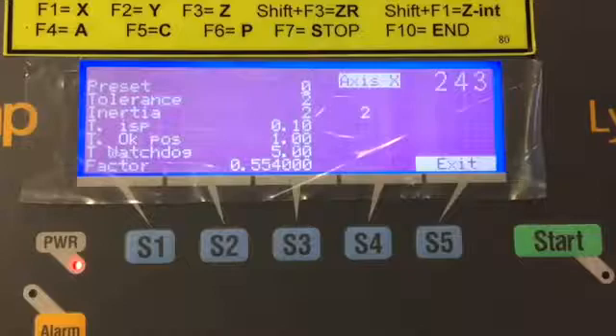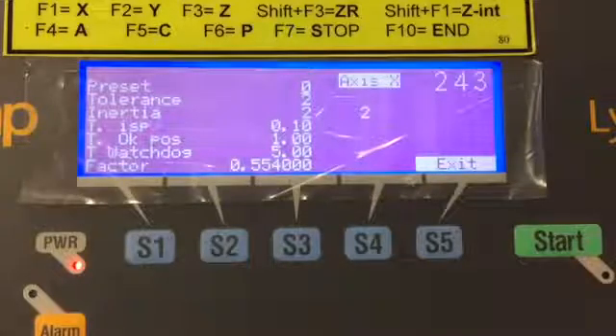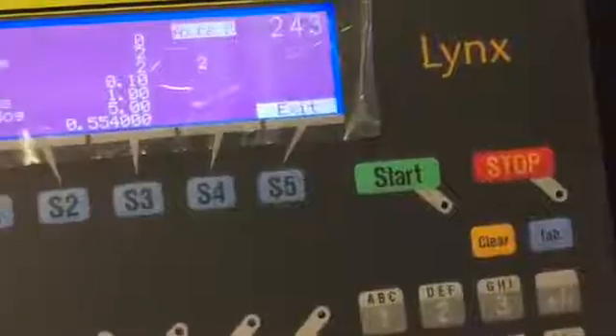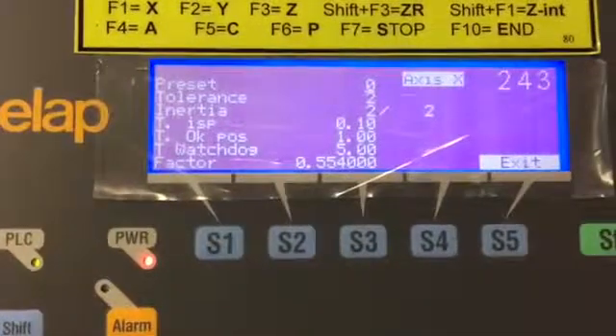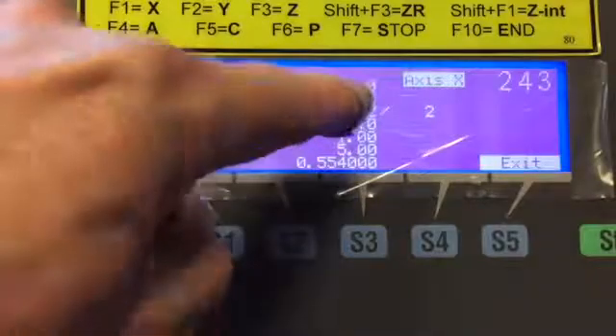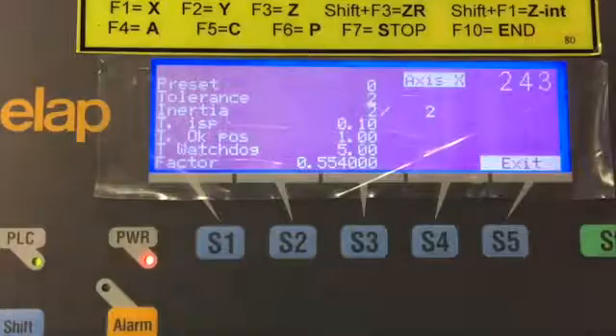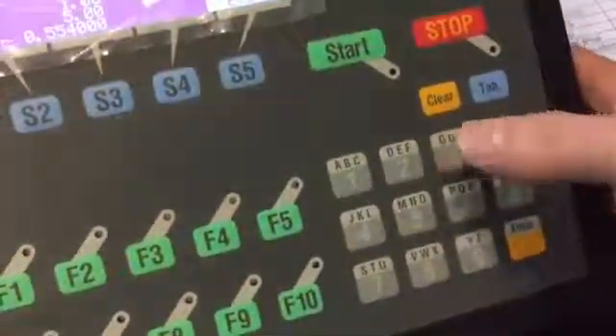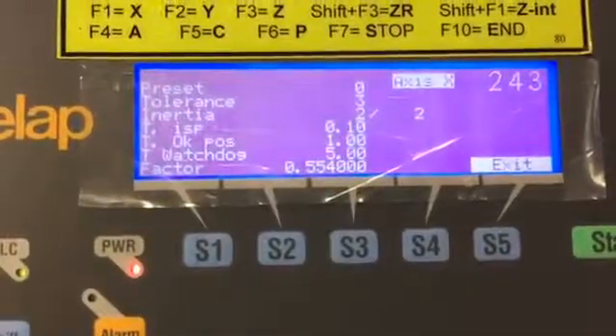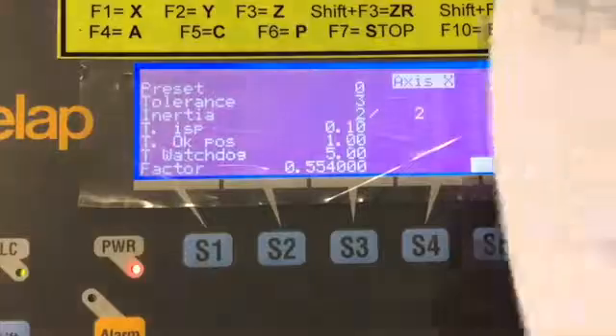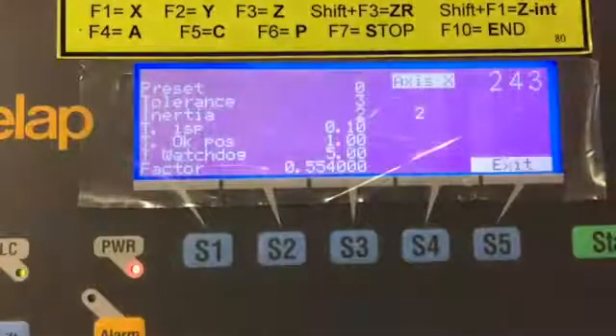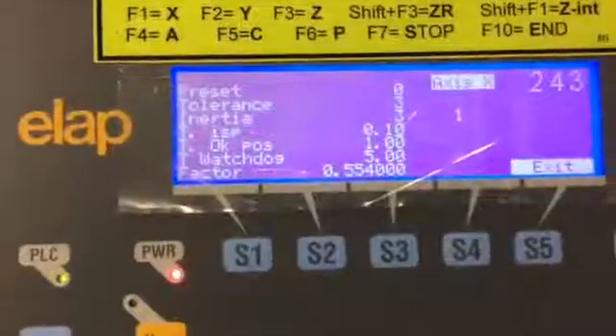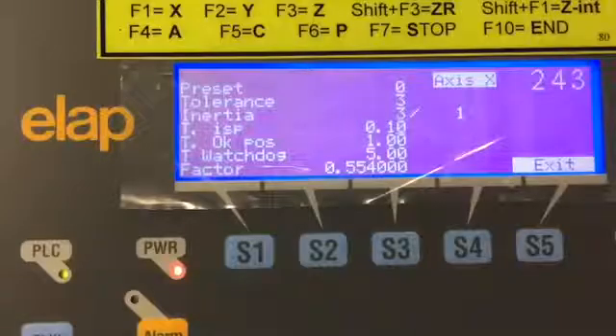To do that you're going to press the tab button on the control, which is located here. We're going to scroll to the first one to insert which is the tolerance. You can see the cursor flashing here. If I press tab it moves to the tolerance and it's flashing. On our sheet we have a value of 3. We're just going to go ahead and use the keypad here. We're going to press 3 and press enter. Now we can see that our tolerance has changed to 3. For the inertia we have two values there, 3 and 1 on our paper. So we're going to enter 3, enter, and 1, enter. You can see that we've changed the values.